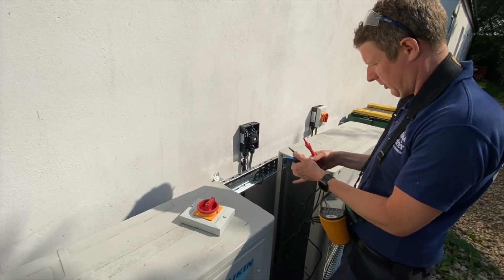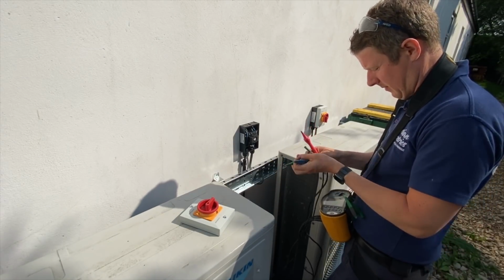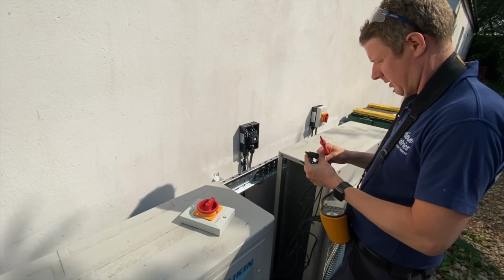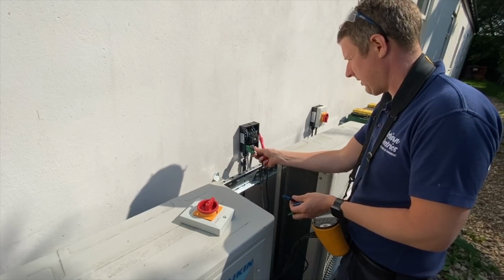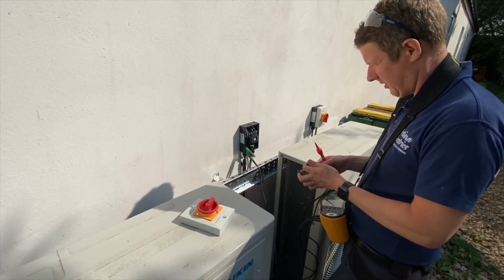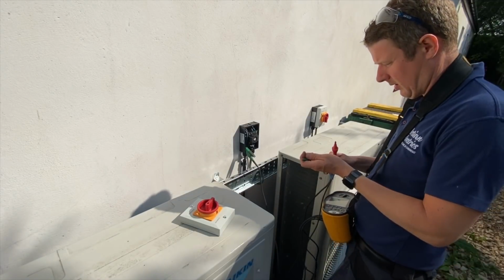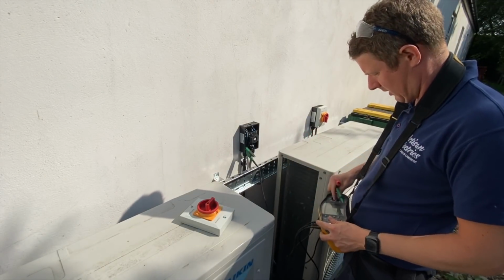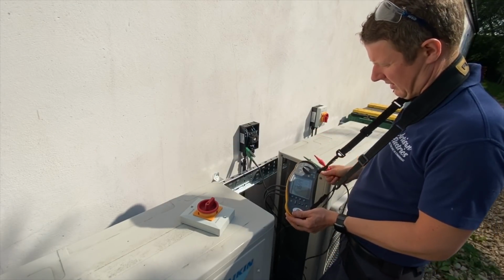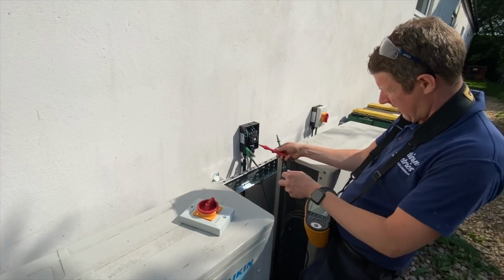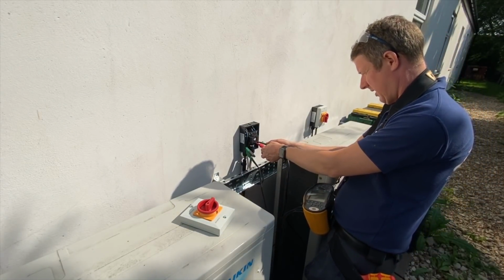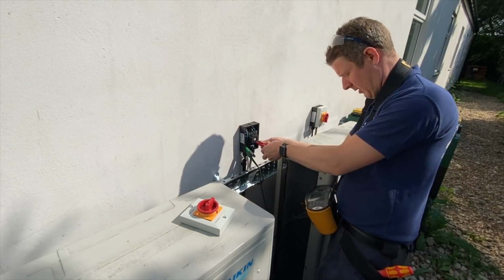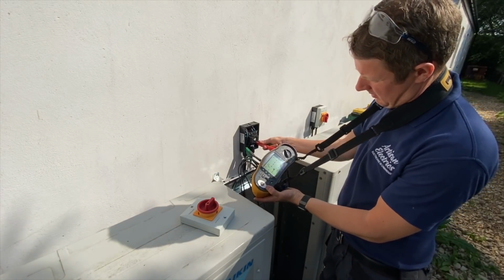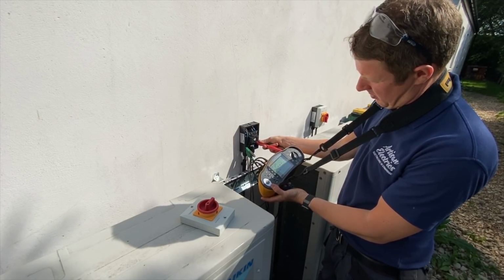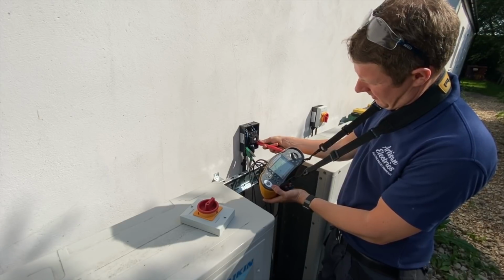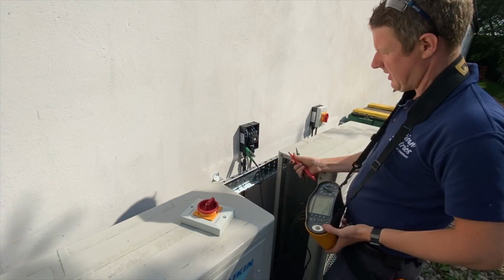So I've got my crocodile clip, which I'm going to put on the earth conductor, and then I can clip that onto the earthing terminal there. For the phase and neutral conductors I will use my dab on leads, setting it to the non-trip setting as it's got RCD protection on the circuit, going onto the incoming side of the isolator, and we have power. So I press the test button, hold the leads on nice and firm, and we've got a reading of 0.43 ohms, which is excellent.